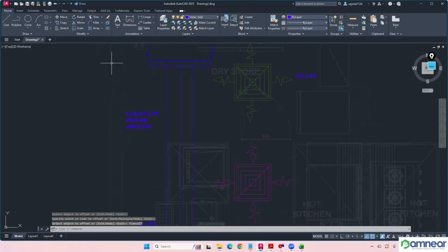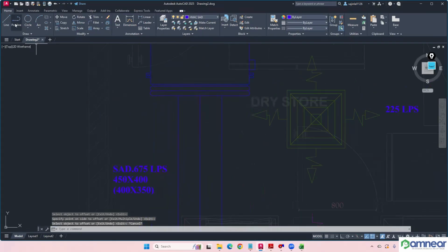Okay. Let me make that 450 under. 450 means 225 under here and 225 here. Mouth angle 45 maximum as per DW 144. So just shift at an approximate distance of, let's say, 400, angle 315. Yeah, double under. Okay, you can mirror this one.